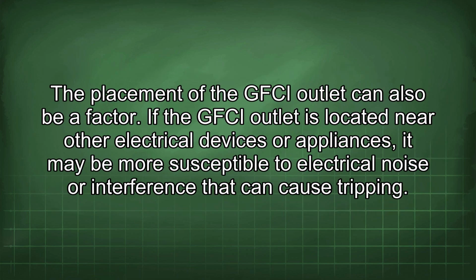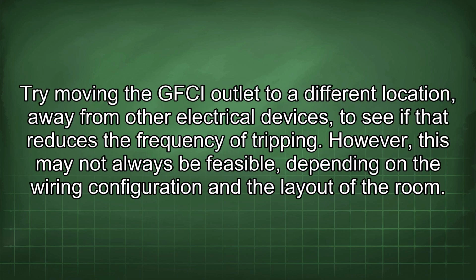The placement of the GFCI outlet can also be a factor. If the GFCI outlet is located near other electrical devices or appliances, it may be more susceptible to electrical noise or interference that can cause tripping. Try moving the GFCI outlet to a different location, away from other electrical devices, to see if that reduces the frequency of tripping. However, this may not always be feasible, depending on the wiring configuration and the layout of the room.